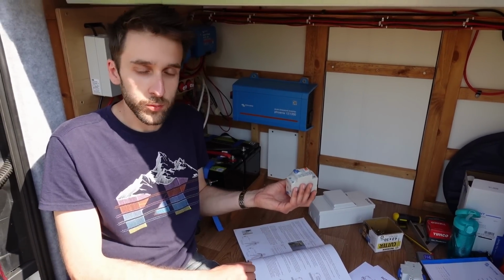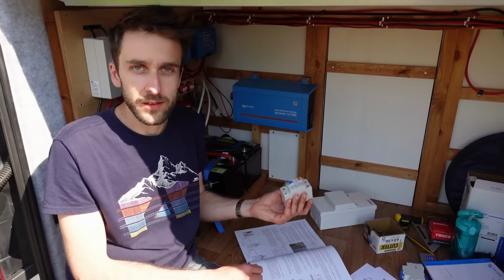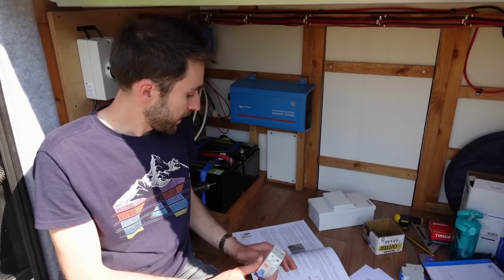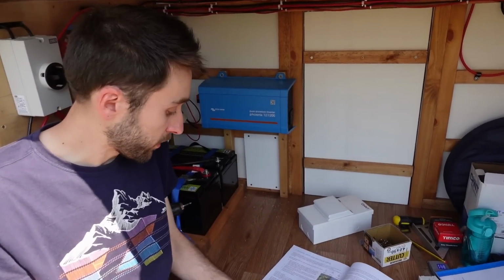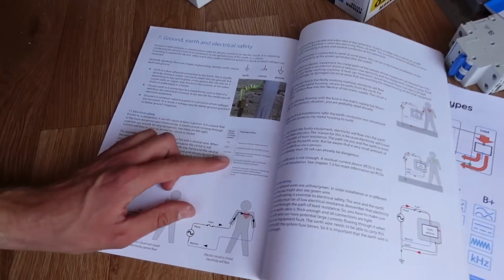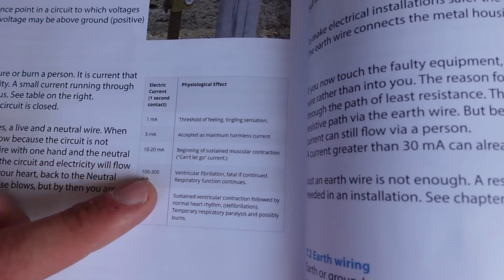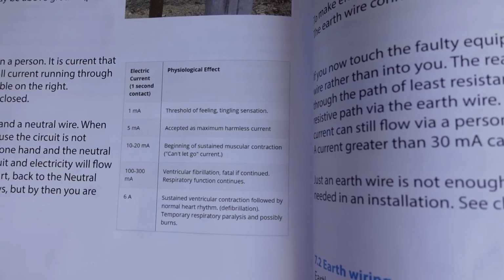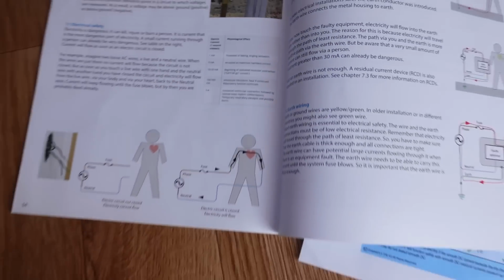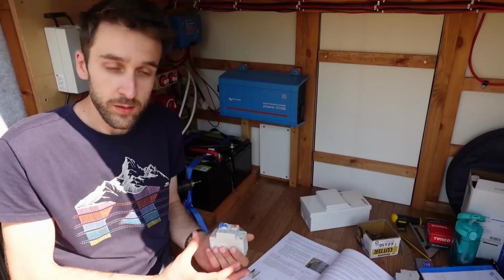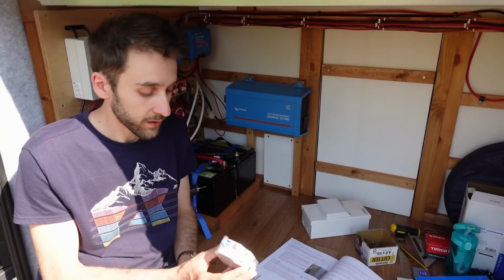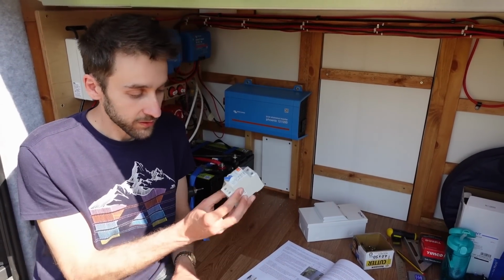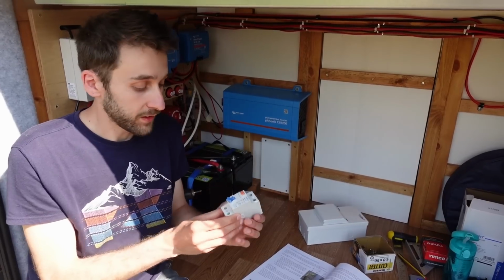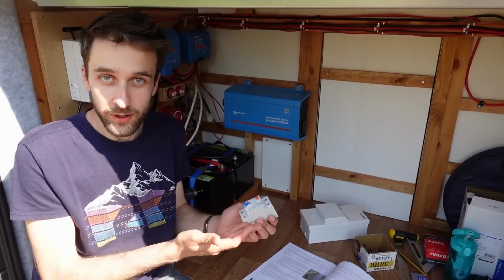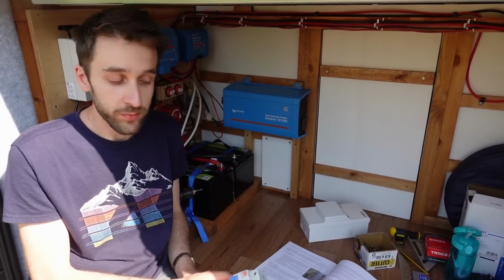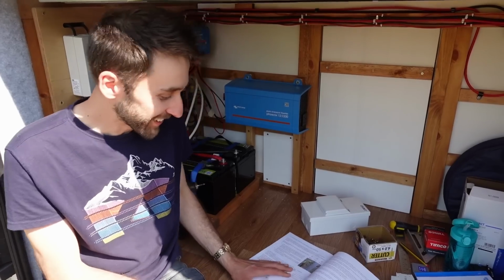Even something as small as 1 milliamp, which is nothing, is enough to actually feel it, a bit of a tingling sensation, and it varies depending on the person, but as a general rule of thumb, even 10 to 20 milliamps, which again is really not much, is enough that you already can't let go. Once you start getting up beyond that it can obviously be really bad and potentially fatal. So what this does is detect that and switch, hopefully straight away, so you don't have any problems and you live another day.